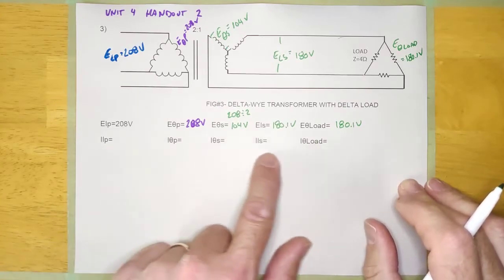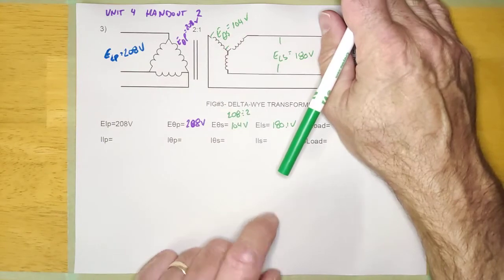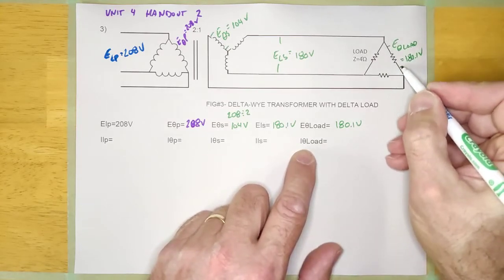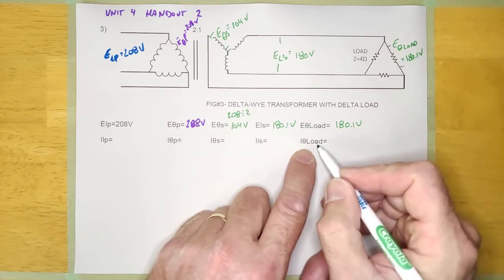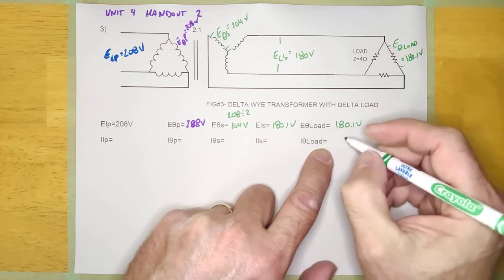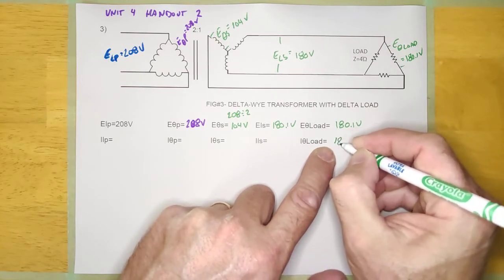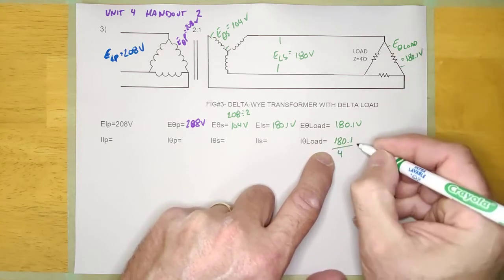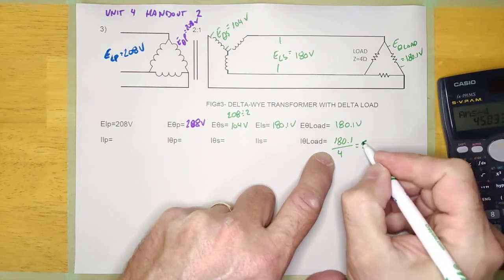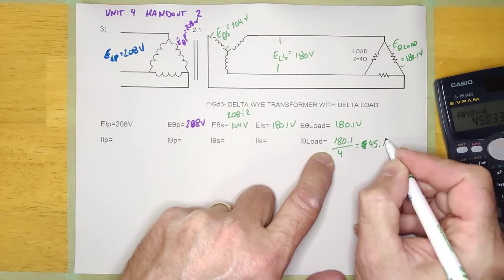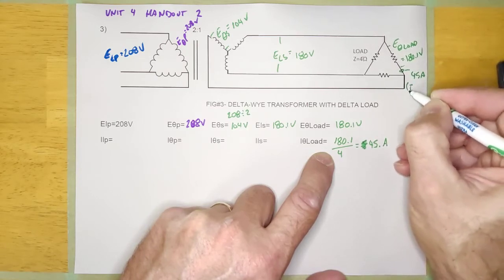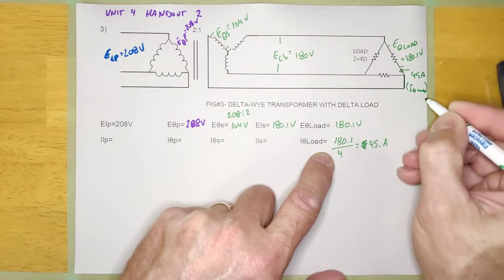Now it's asking about all these currents. Up until now we haven't had a load on there, but now we're going to actually calculate the current. E-phase load is 180 volts and the impedance is 4 ohms, so I'm going to use Ohm's Law: I equals E over Z. So it's going to be 180.1 divided by 4, and that equals 45 amps. That is I-phase load — 45 amps.